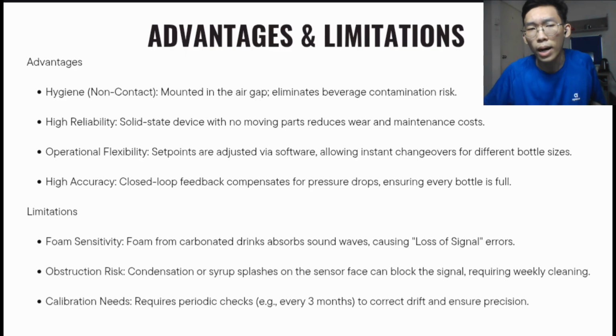However, we must manage the 3 specific limitations, which is foam sensitivity. The heavier foam can absorb the sound wave, potentially causing a loss of signal. The second one is obstruction. Condensation or syrup splash on the sensor face can block the sound pulse. The last one is calibration. Since it relies on the speed of sound, periodic calibration is required to prevent measurement drift.